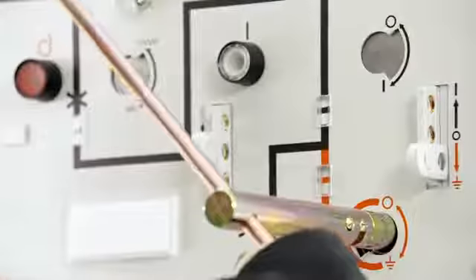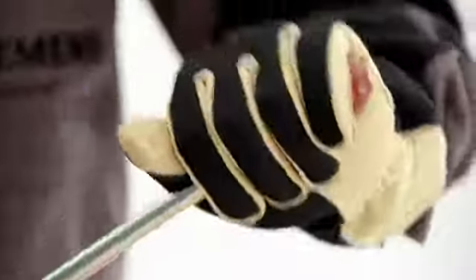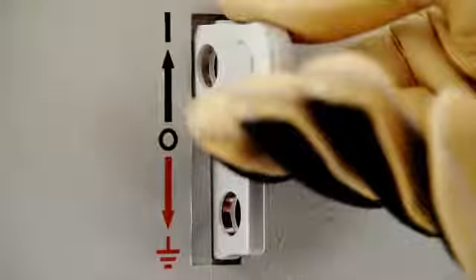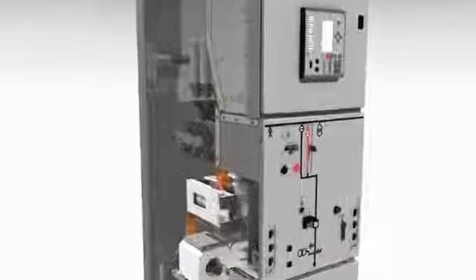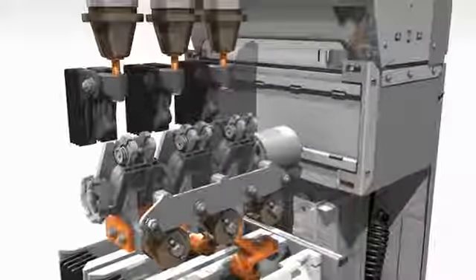Behind the gas-insulated medium-voltage switchgear by Siemens stands an operational concept thoroughly thought out in every detail, since the equipment has been designed to guarantee the highest level of personal safety. Even under difficult conditions, the superior technology with its circuit breaker and 3-position switch masters all the requirements for every switching procedure.